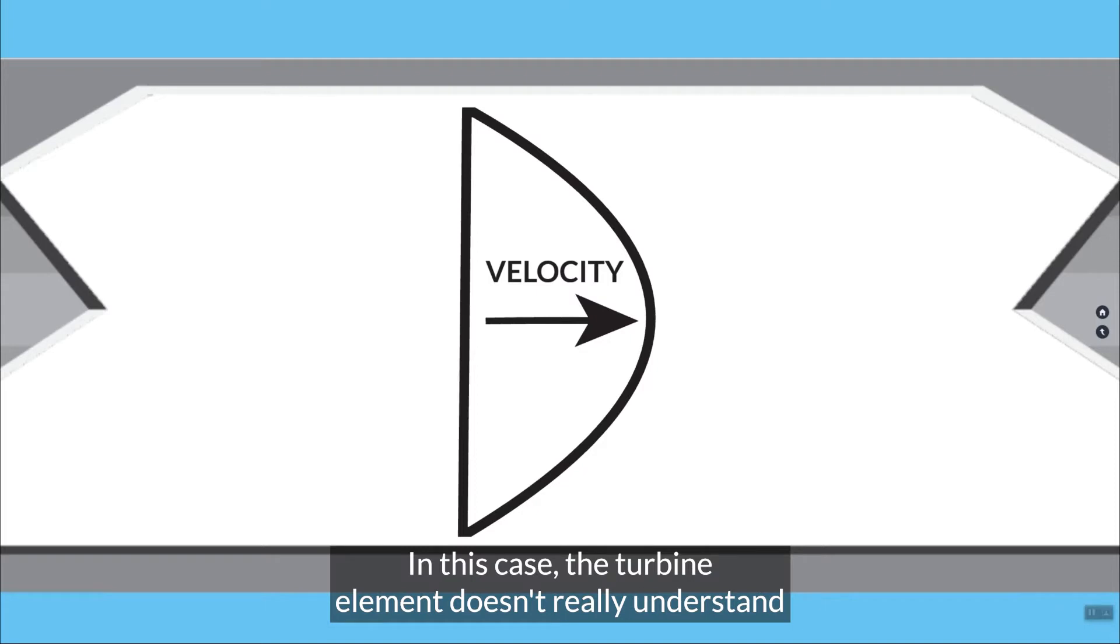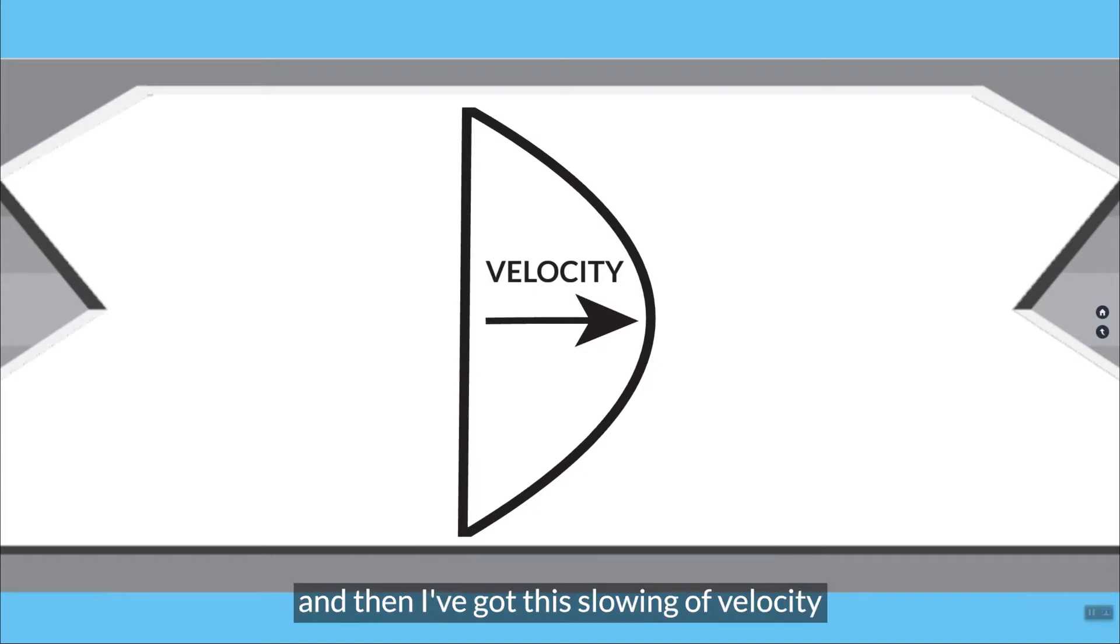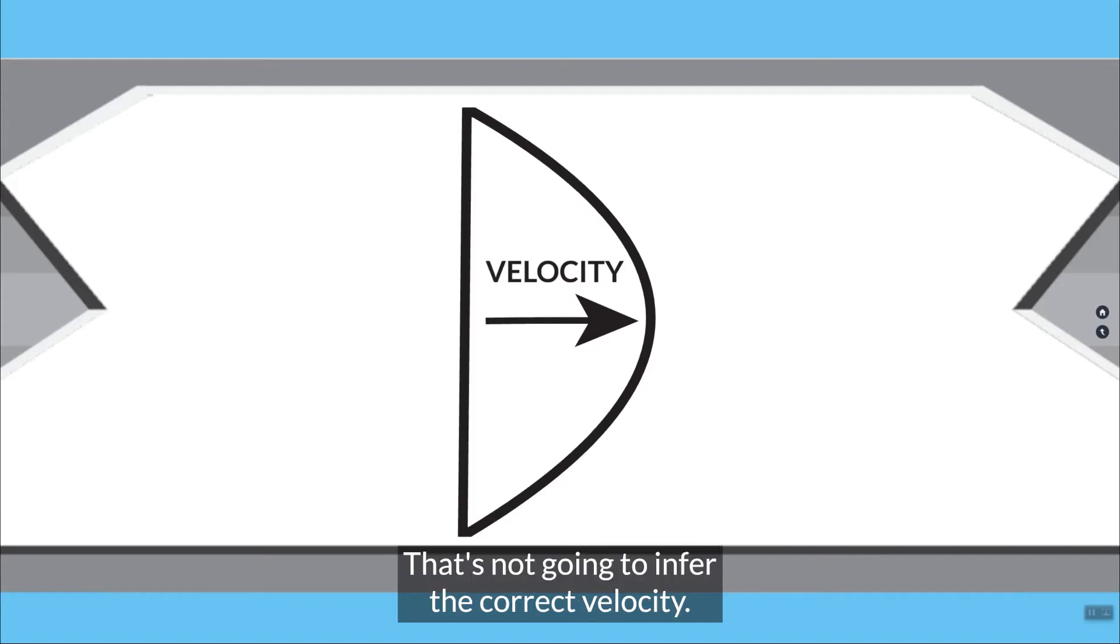This is not what we want. In this case, the turbine element doesn't really understand what it's supposed to do here. I've got this over-speeding towards the middle of the pipe, and then I've got this slowing of velocity near the top and bottom. That's not going to infer the correct velocity.